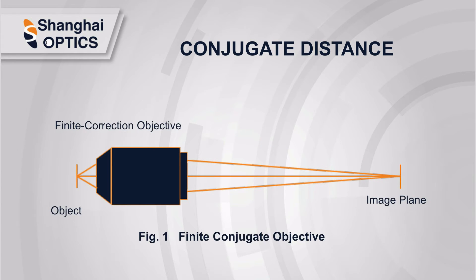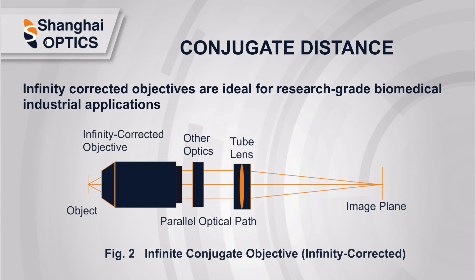Using a finite conjugate objective, as shown in Figure 1, is a good economical choice for a simple microscopy system. Infinity corrected objectives are ideal for research grade biomedical and industrial applications, especially when additional components such as filters, dichroic mirrors, or polarizers are needed. Adding optical plate components in the infinity space between the infinity-corrected objective and tube lens will not introduce spherical aberration or change the objective's working distance.